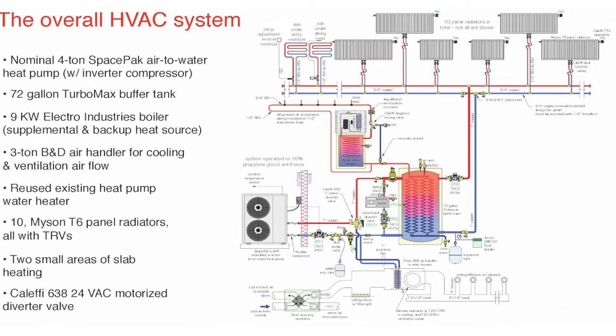Now, that tank, the TurboMax tank, has those internal copper coils, you can see them over here. We feed our cold domestic water into those coils, and we're using that for preheating. We can bring that water up to about 100 degrees with this tank. Now, we could set the heat pump to bring it up to a higher temperature, but the existing building had a 2-year-old heat pump water heater that was working great.